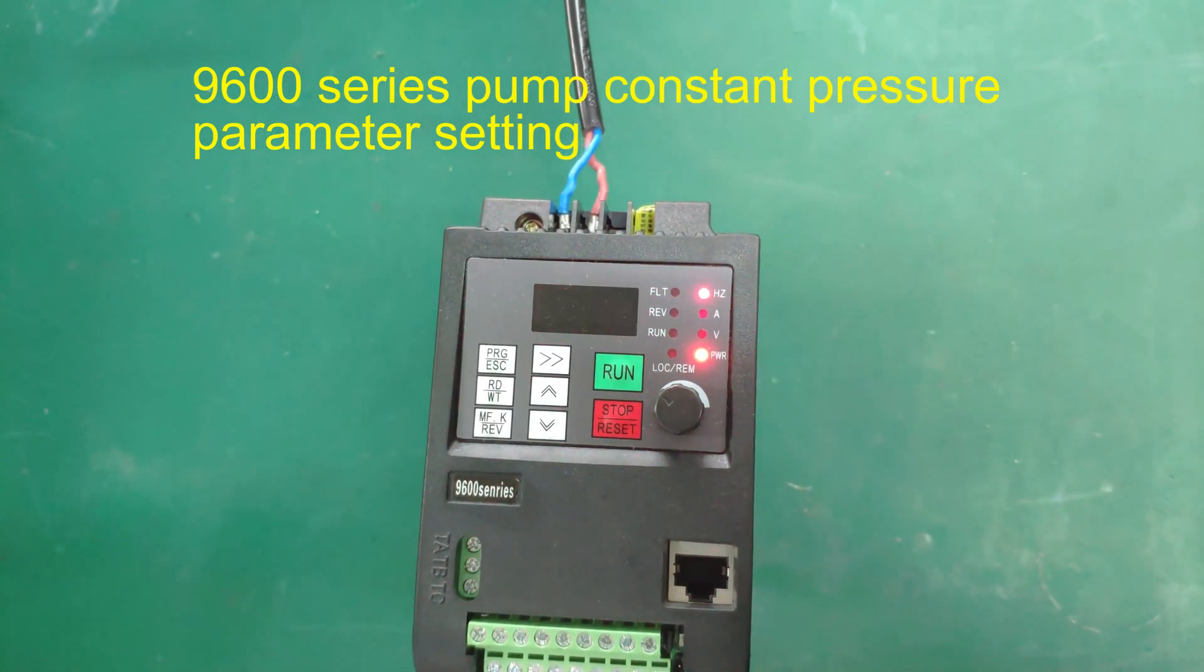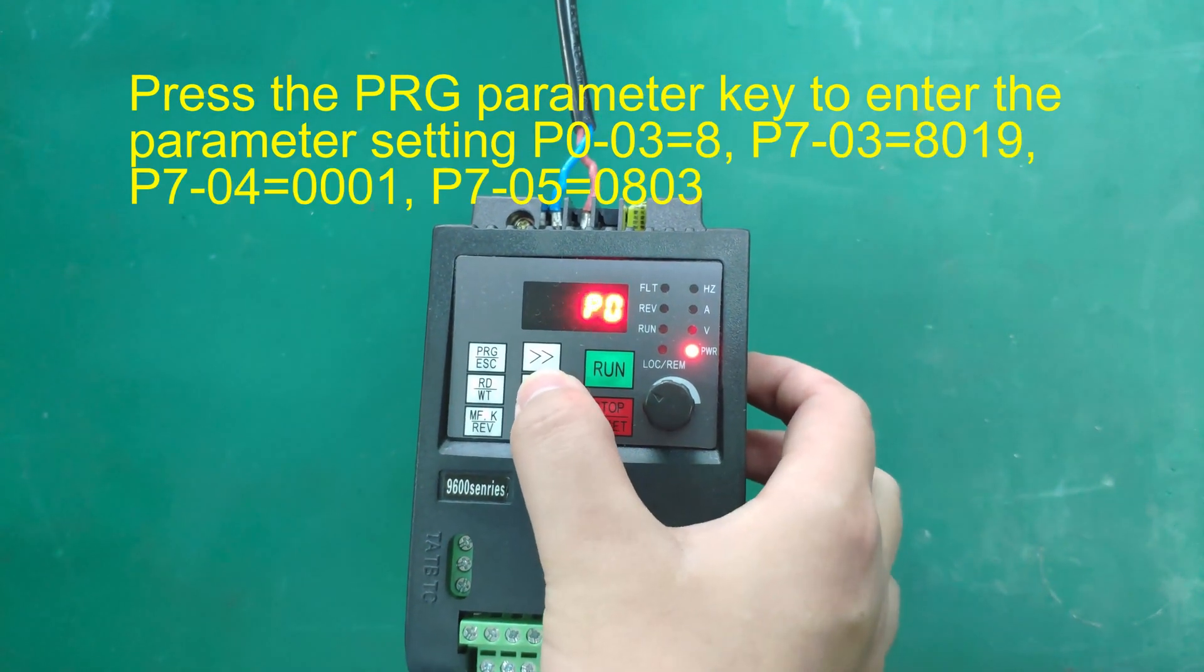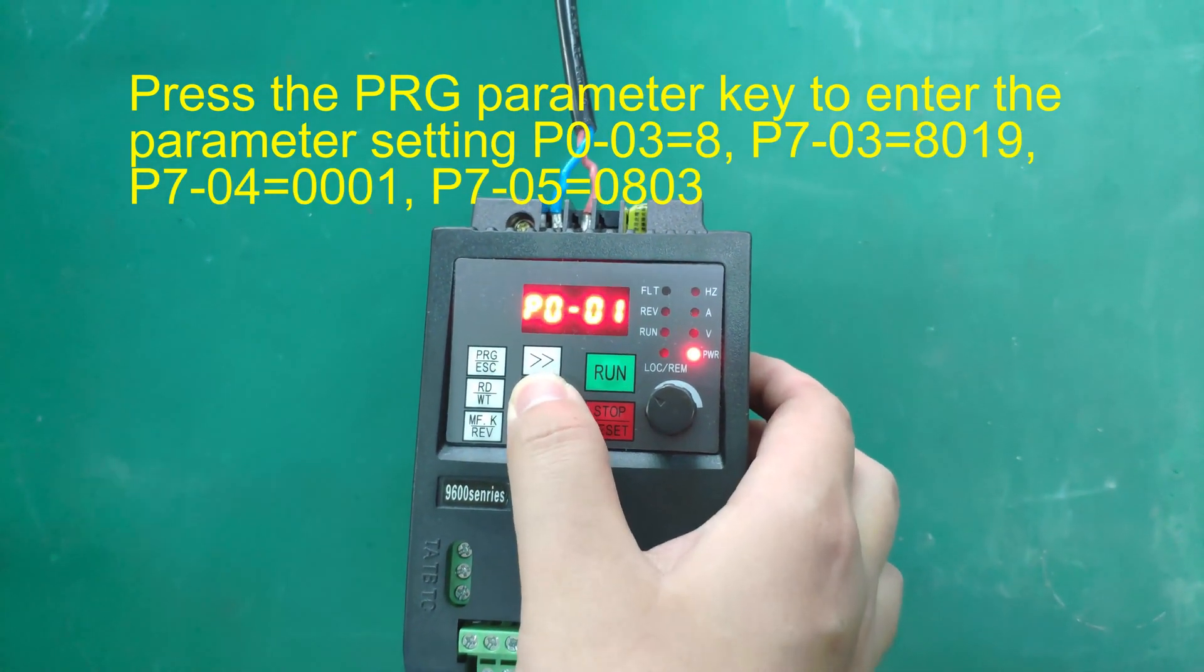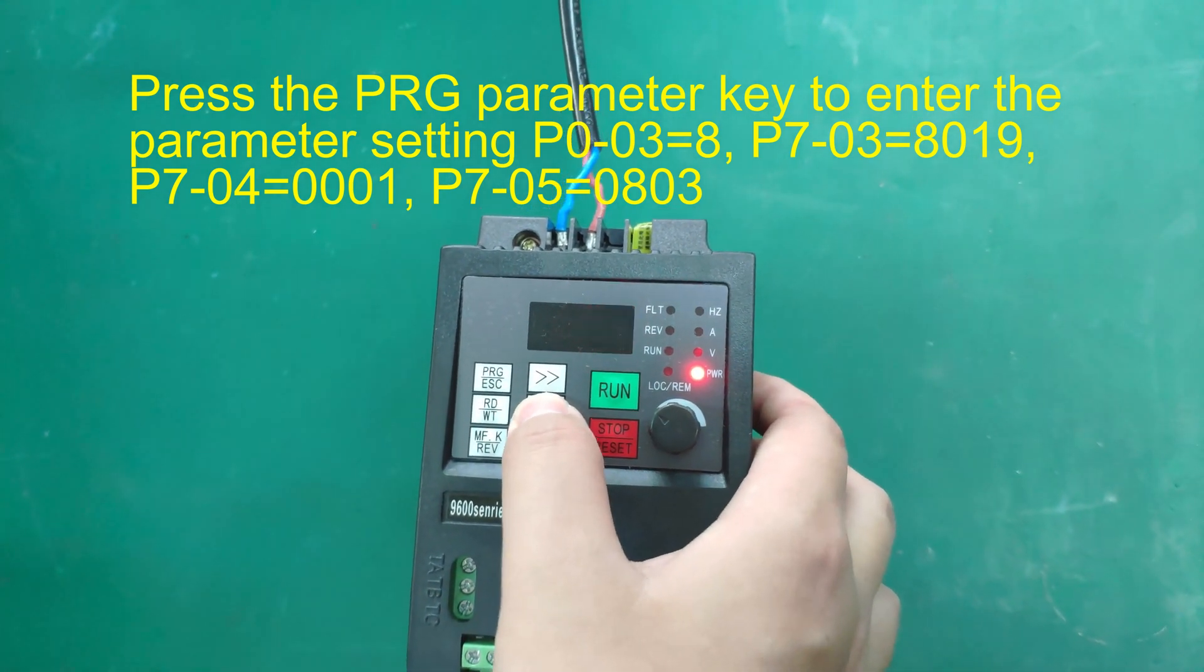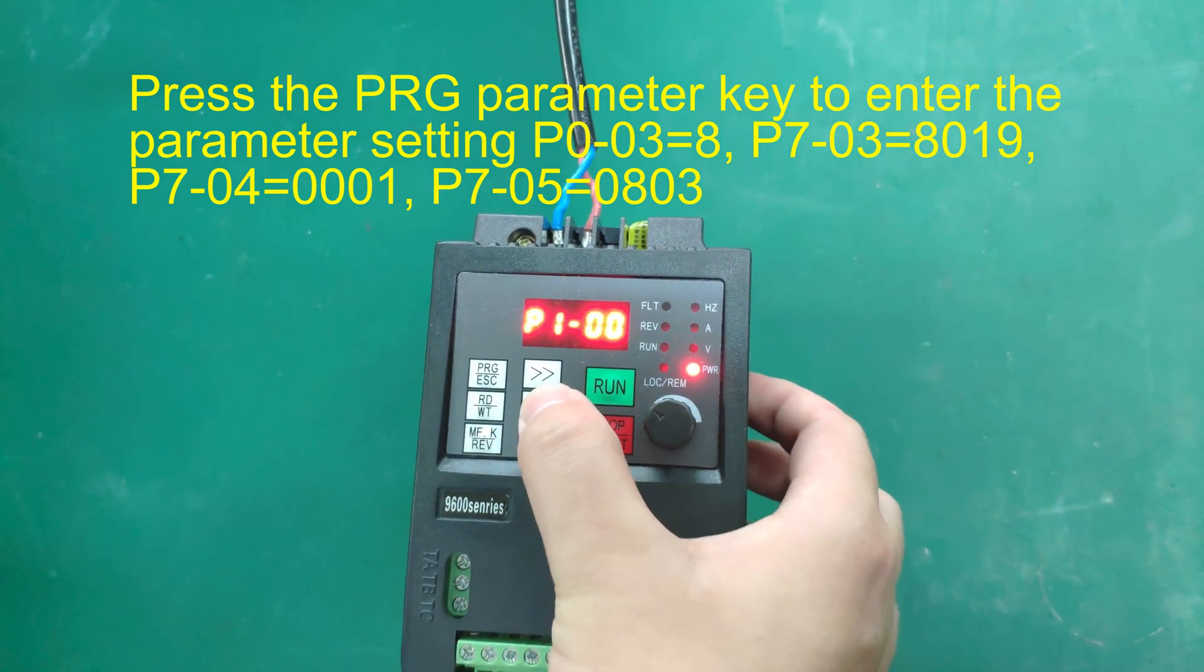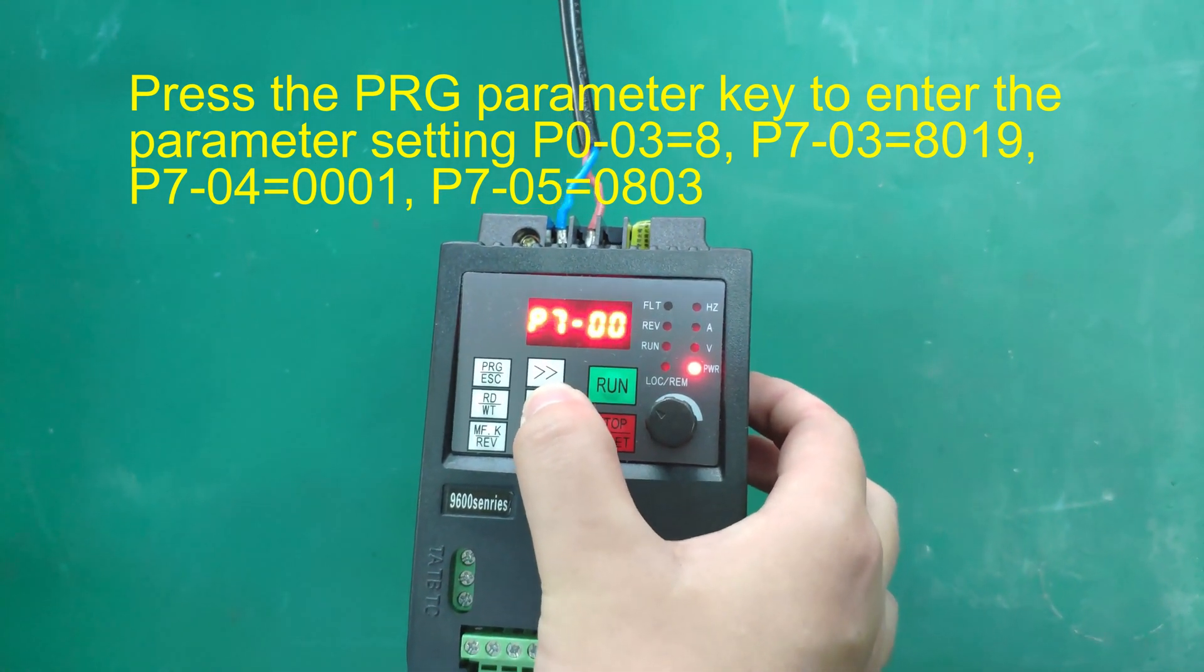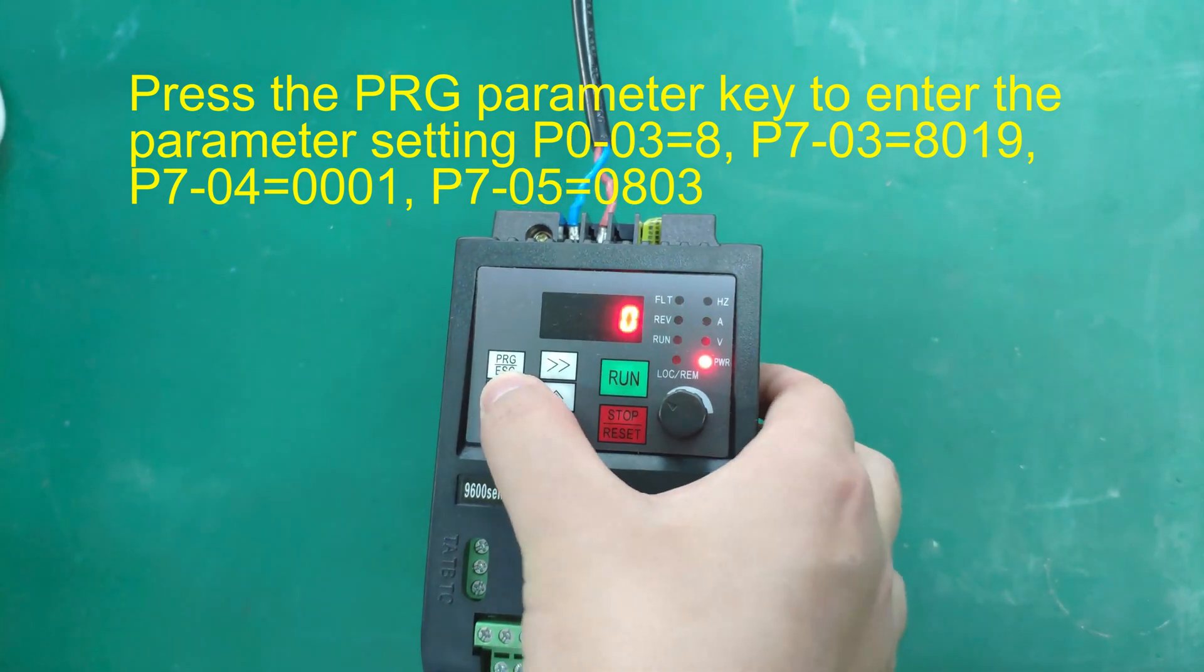9600 Series Pump, Constant Pressure Parameter setting. Press the PRG parameter key to enter the parameter setting: P0-03=8, P7-03=8019, P7-04=0001, P7-05=0803.